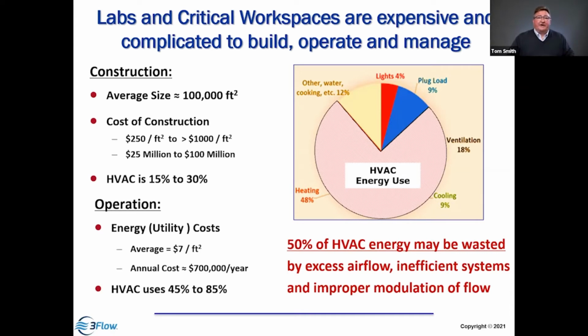And what we have found through working with Lawrence Berkeley and an International Institute for Sustainable Labs and US EPA and others is that as much as 50% of that energy may be wasted by improper modulation of flow and inefficient systems. So we really need to think about how do we manage the airflow to minimize cost but meet the safety requirements of the occupants.